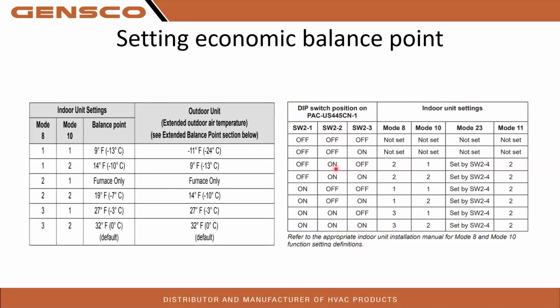So like I said, if you're using the PAC 445, it's very important that you make sure to set these up. If you don't, the system does weird stuff. Fans don't want to run, the system doesn't want to work the way it's supposed to. It's going to do crazy things. So this is one of the things we usually check on the phone if you're using 445s. Make sure your balance points are set up.